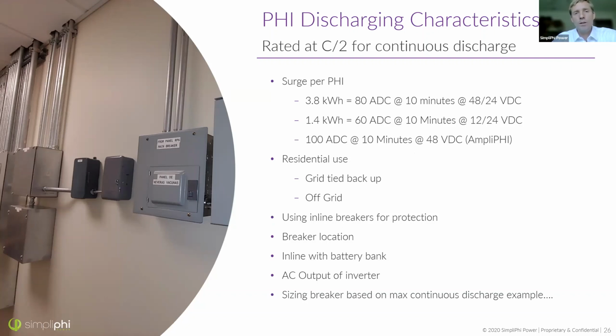And the reason is that when you're discharging at a really high rate like this, it produces heat inside the battery cells, right? And if you do that for too long, the battery cells can get hot and then you can start to cause damage. So temperature can damage the cells with time, but they do offer you a surge, 80 amps for 10 minutes. And that's a little bit more than 4 kilowatts of power per battery. If you have multiple batteries, that number multiplies as well. Okay, and then the AmpliPHI battery, as you can see on the bottom, has a 100 amp surge. And the 1.4 kilowatt battery, the smaller one we offer, has 60 amps of surge.